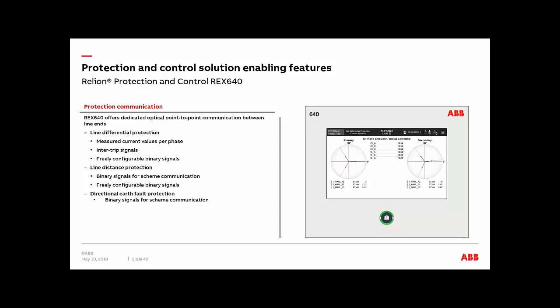And if you have directional earth-fault protection, you can also have binary signals available to you from relay to relay as well. And we keep the same situation here where the communication distances are up to 50 kilometers possible with full supervision of the channel of communication, so you can detect the loss of the link between devices.